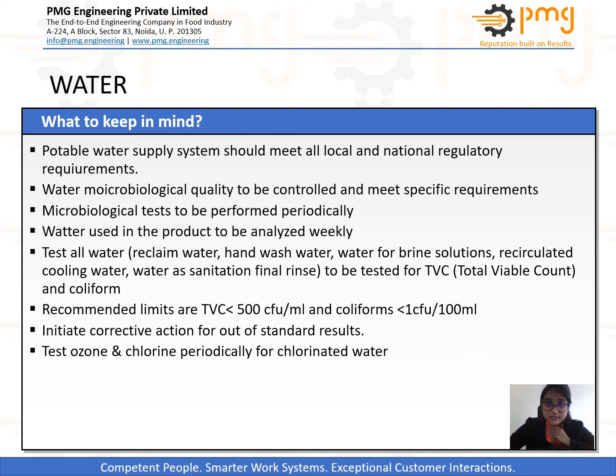Potable water supply systems should meet all local and national regulatory requirements. Water microbiological quality to be controlled and meet specific requirements by performing periodic microbiological testing. Testing of all water — including reclaimed water, hand wash water, water for brine solutions, recirculated cooling water, and water used as a final rinse — to be tested for TVC and coliforms. Corrective actions to be initiated for out-of-standard results. Ozone and chlorine to be tested periodically for chlorinated water, and weekly analysis to be conducted for water used in the product.